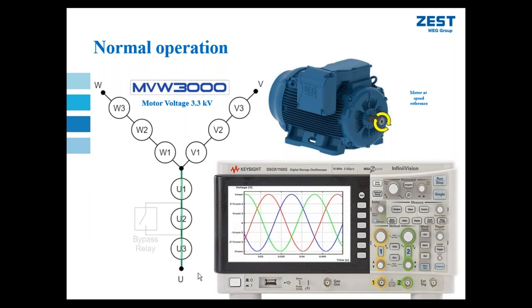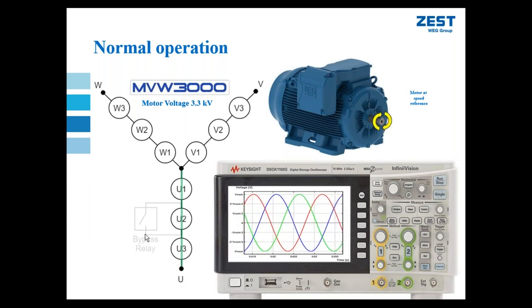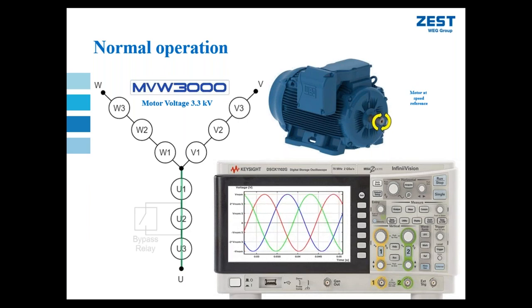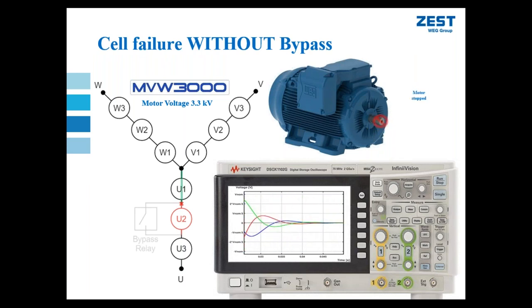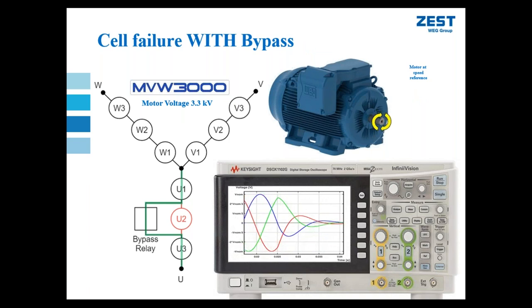Here we have all our power cells healthy. We're showing all three output phases to the motor. But let's say in the U phase, we have a faulty power cell. Then the drive would automatically disable and stop providing voltage from all three phases to the machine. We can bypass the faulty power cell, we would then reduce the output voltage from this U phase. This would result in an imbalance between the three phases. So using software algorithms, we also reduce the output voltage in the other two phases in order to achieve a balanced three-phase output voltage to the load. But the voltage capability is reduced. So if it's a fan or something that can be run at a reduced speed, it's possible to run the load even at a slightly reduced voltage output.